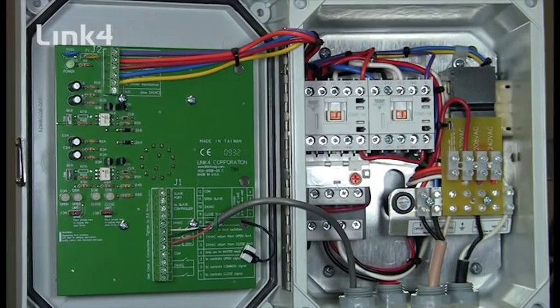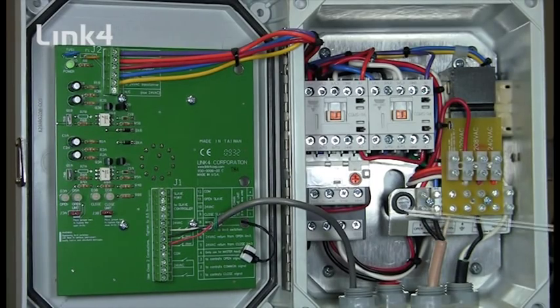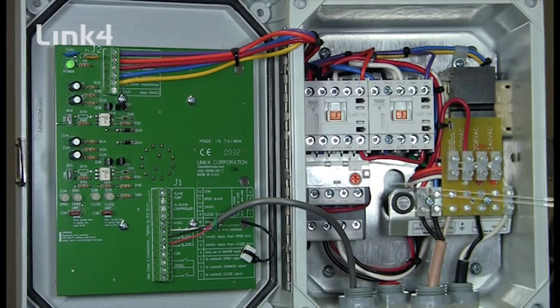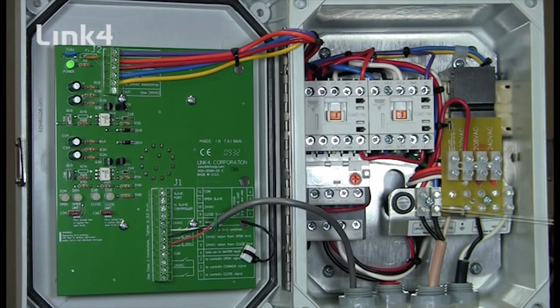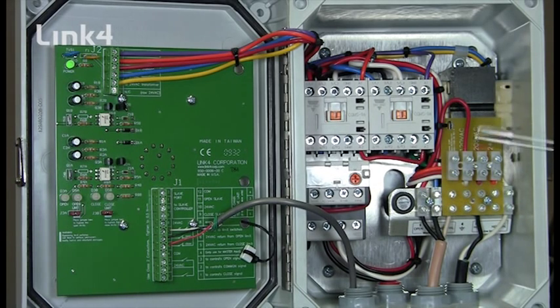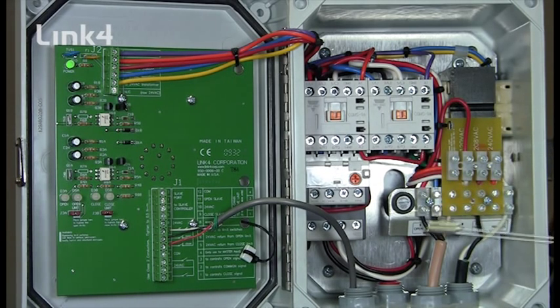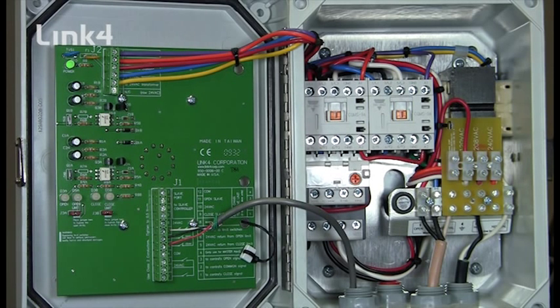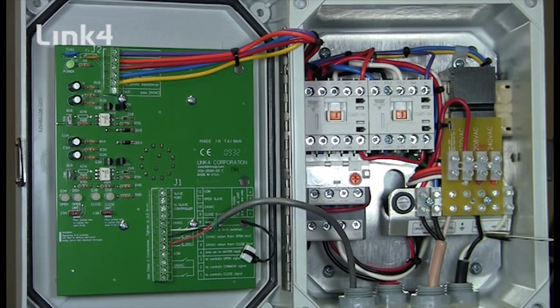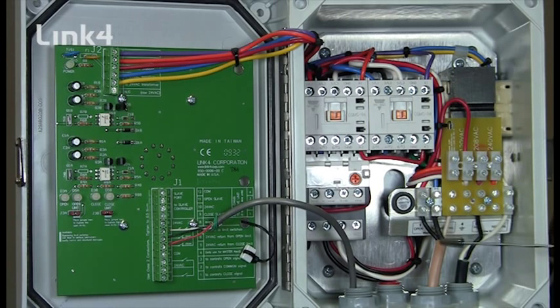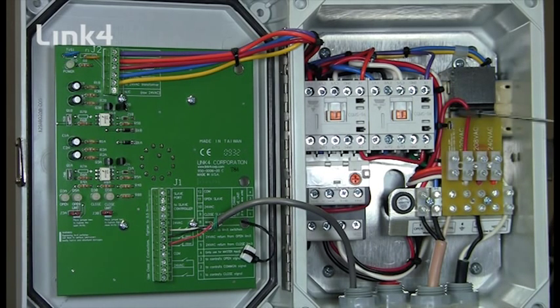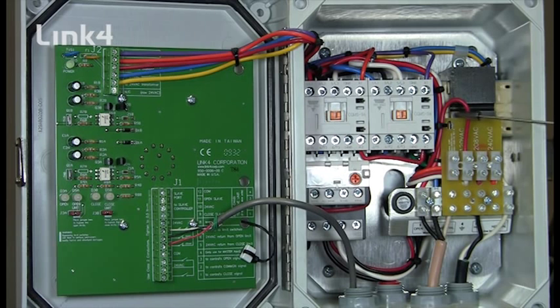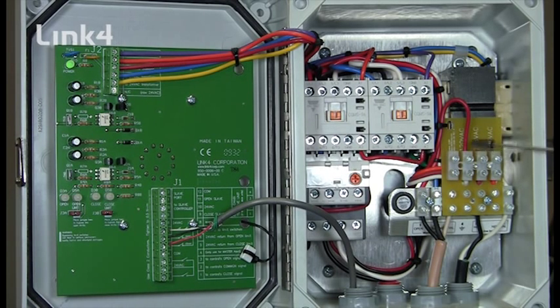Now that we're ready to wire the iDrive 300 we have to answer a couple questions. One, what type of motor do we have? We know we have the RW45 from Ritter which is a 3 wire motor, 120 volt. So we have our connection wire for the transformer which we must put into the 120 volt slot.